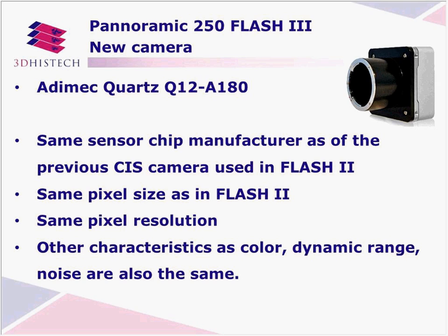The new camera is from Adimec. Adimec is a Dutch company, and we selected the camera on purpose to have the same chip manufacturer as the Flash 2 camera from CI. The purpose was so that we have the same pixel size, resolution, same color, same dynamic range, same noise, so that we provide the very same image quality as we provided with the Flash 2.